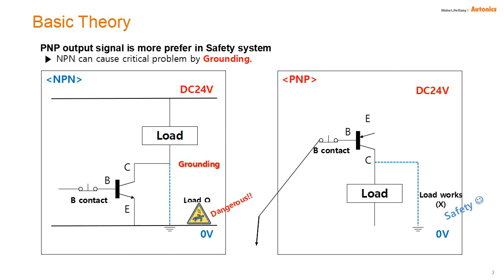Lastly, another safety system preference is for PNP output signal. Why? With NPN output signal, if the wiring is broken and the wire touches the ground, because this is a negative signal, it will trigger something. It is very dangerous. How about PNP? PNP is a positive signal. If it meets this grounding situation, it will not trigger anything. It is safe.